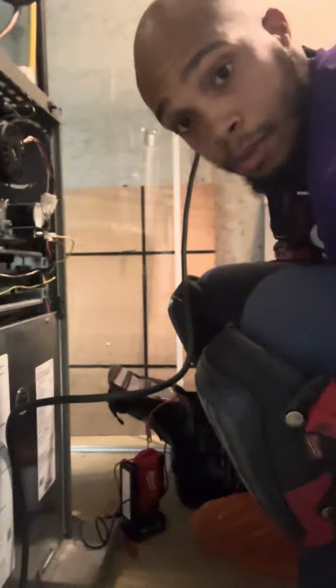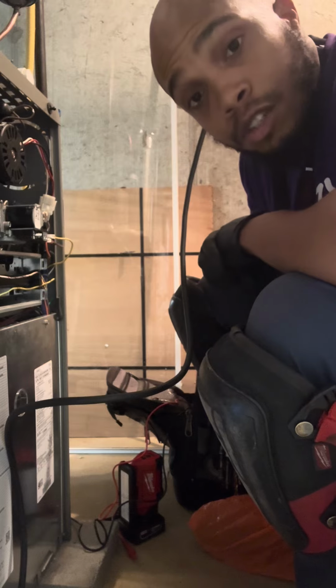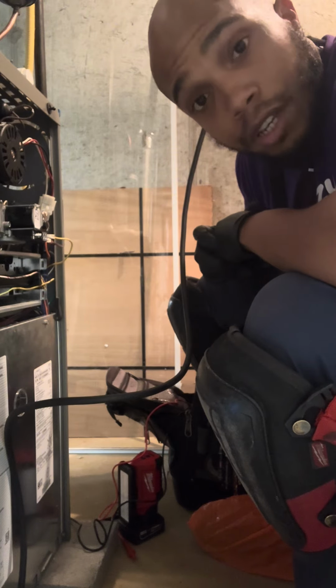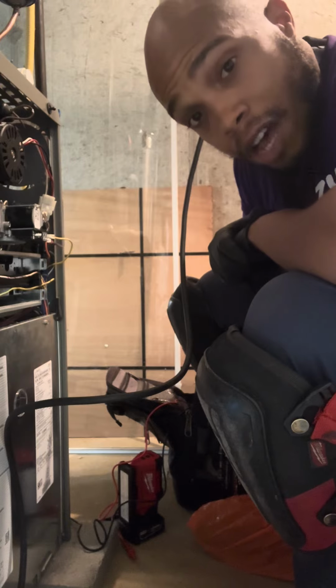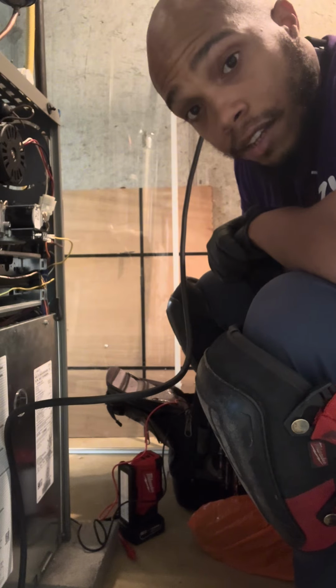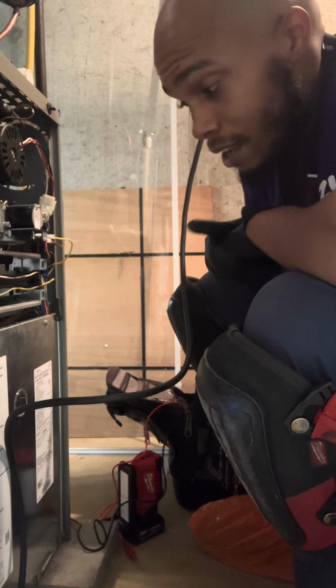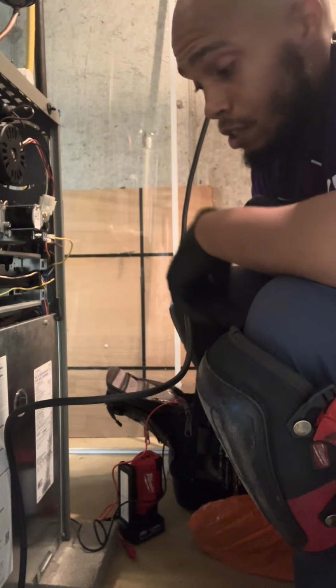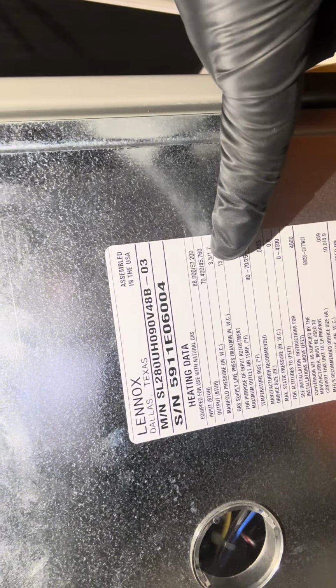On a 2-stage furnace, you should be looking for 1.7 inches of water column in the low stage, and about 3.5 inches of water column in the high stage. That is for natural gas, and that is for this appliance. But don't trust me though. If you ever want to know, you can always look at your system's data chart, and it'll tell you right there. Manifold pressure, 1.7 on low stage, 3.5 on high stage.